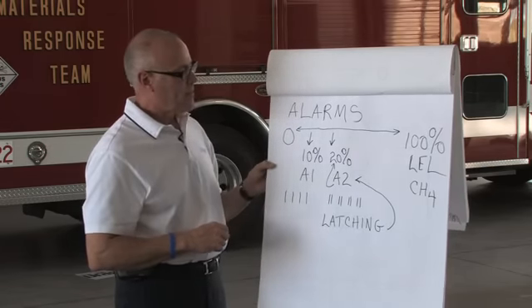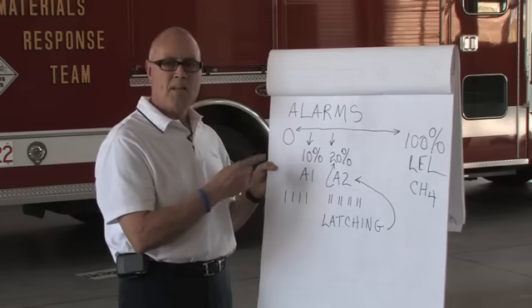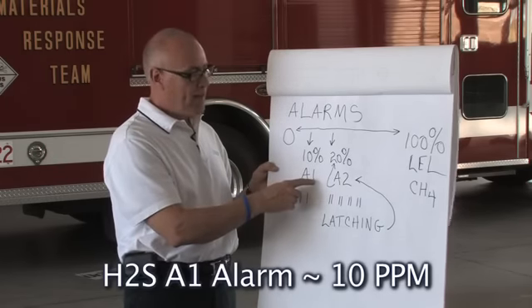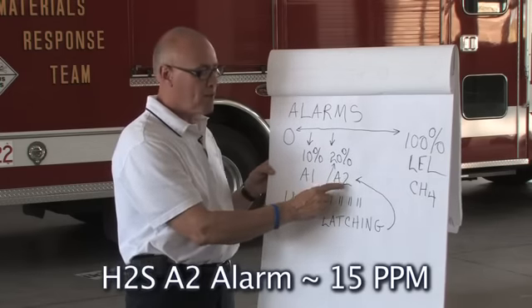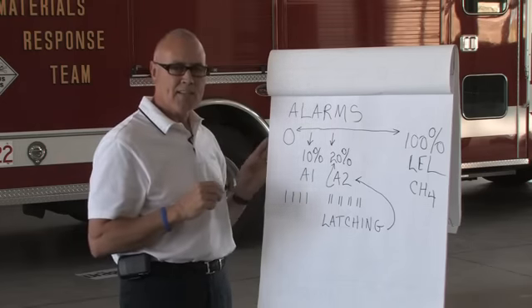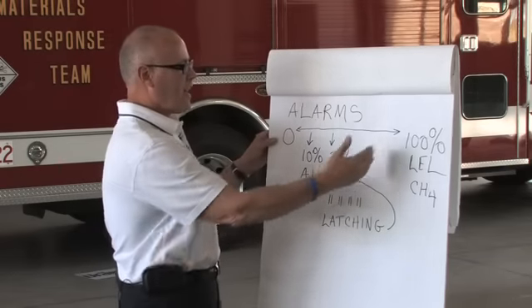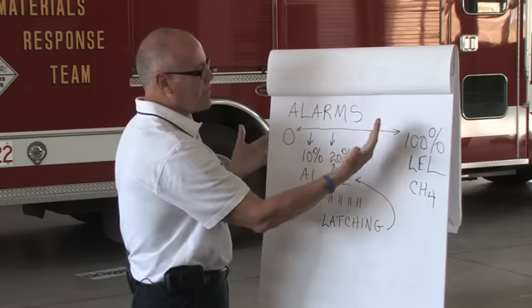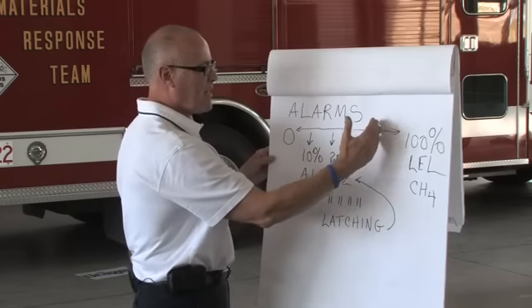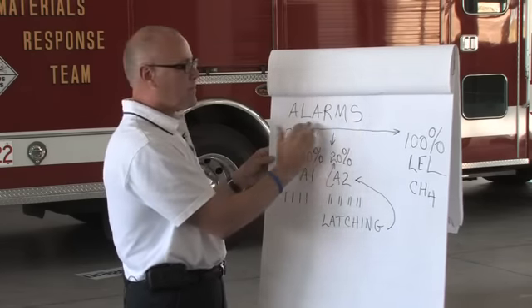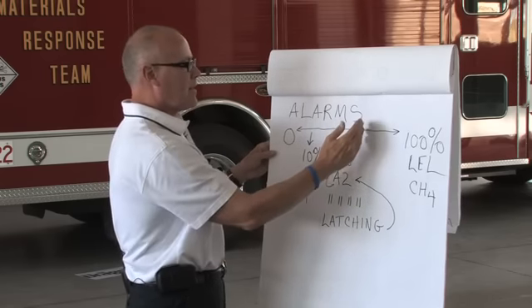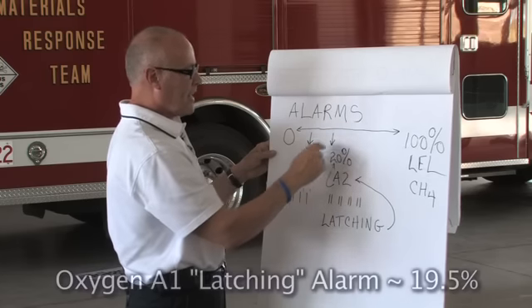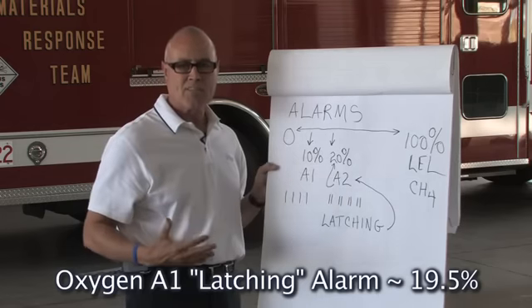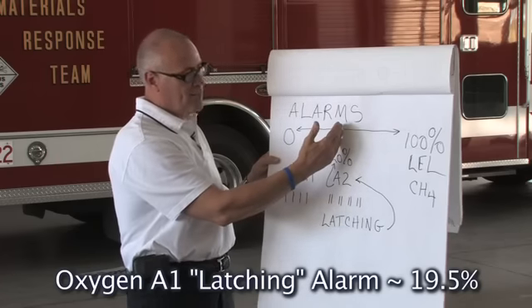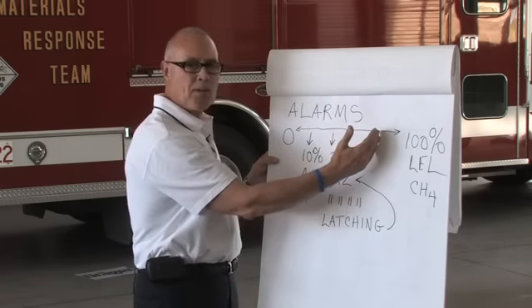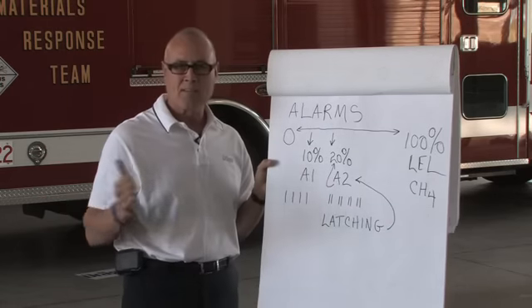And then on hydrogen sulfide, you've got a 0 to 100 part per million scale. You'll get a 10 ppm alarm point, which will be your A1. And then 15 parts per million will be your A2 alarm, which will be your latching. Now, on oxygen, it's flip-flop. On oxygen, you're actually at 20.9, and in most cases, the deficiency of oxygen is the most common alarm. So you're talking about a set point here and a falling of oxygen. So the A1 alarm on oxygen, when you get down to 19.5, you're going to get an A1 alarm, but in the case of oxygen, the A1 alarm latches. So once you hit that 19.5, as you're losing oxygen, and then the oxygen comes back up to 20.9, the A1 latches, and again, you've got to push the big button to silence it.